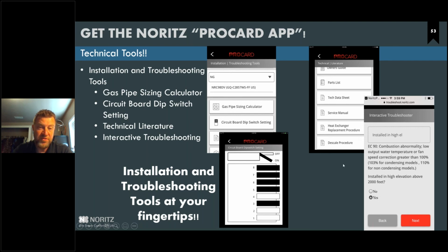There's also an interactive troubleshooter, so if you do get an error code, you can actually put that error code into the interactive troubleshooter, and then it'll give you step-by-step instructions on how to fix that error code. So like this one's a 90 code, which is a combustion abnormality. It's going to walk you through step by step. So like this one's going to say, is this installed above 2,000 feet? You hit yes, you hit next. It'll walk you through how to make sure that it's set for high elevation. So it's a pretty cool app. We have a ton of installers that use it every single day. It saves people bacon quite a bit.